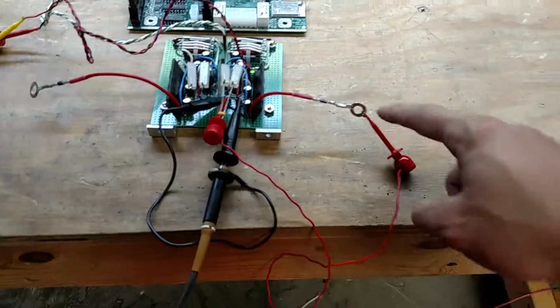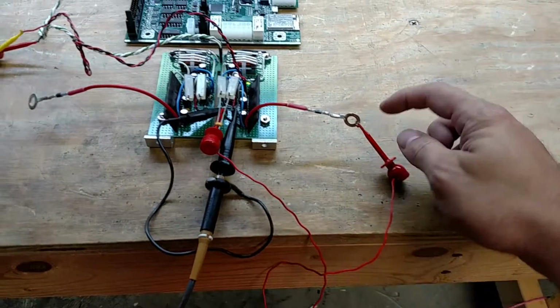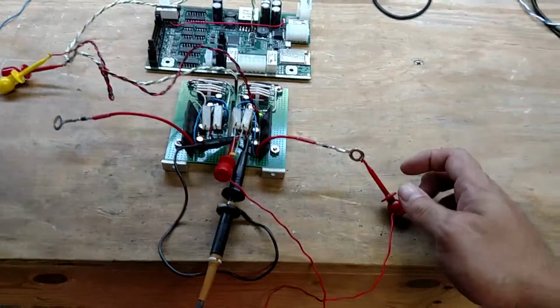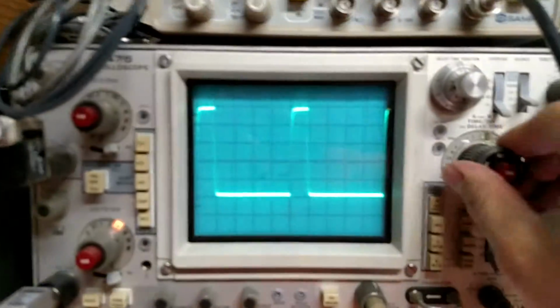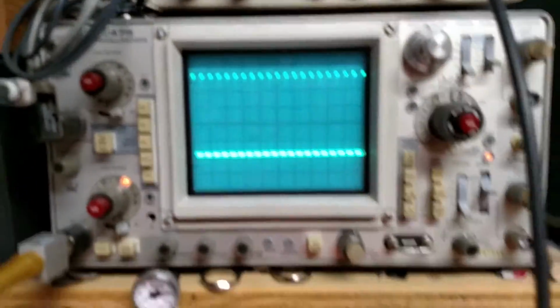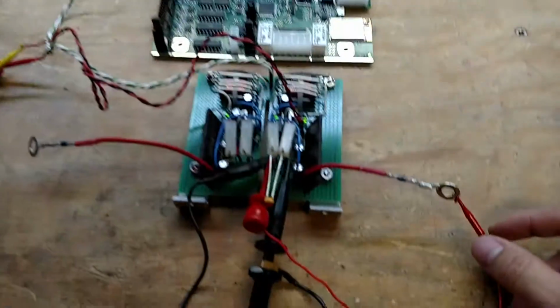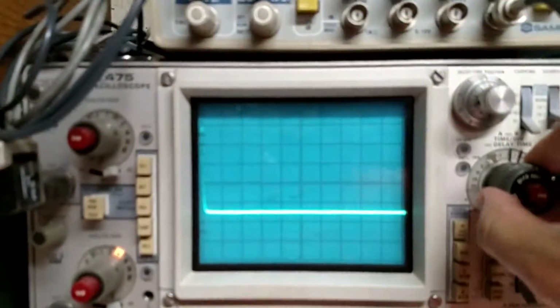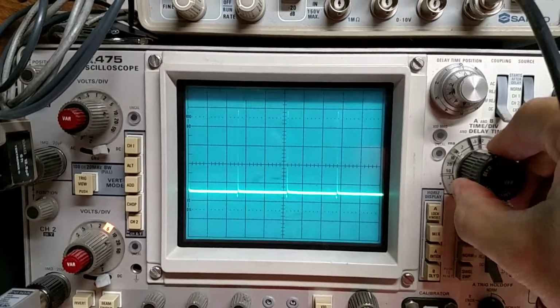What was I going to say? Oh, yeah. So you can see I've got a clip lead going between here. This is the saturation protection circuit. So if I were to, we'll go ahead and expand this out really far. What I'm going to do is actually unplug it. And now it thinks that the MOSFET, or the IGBT, is saturated.